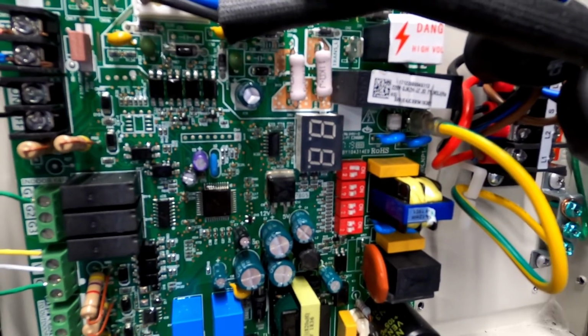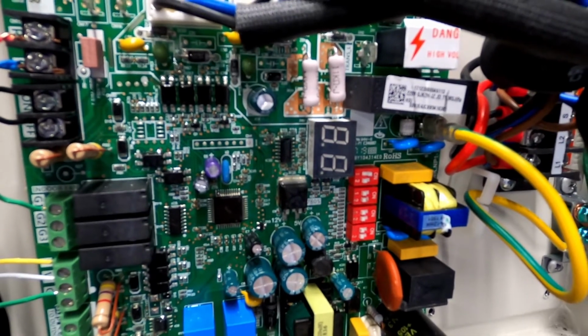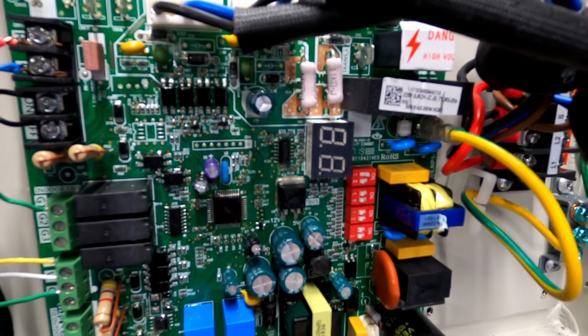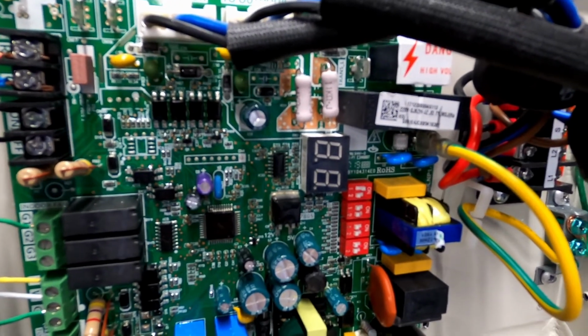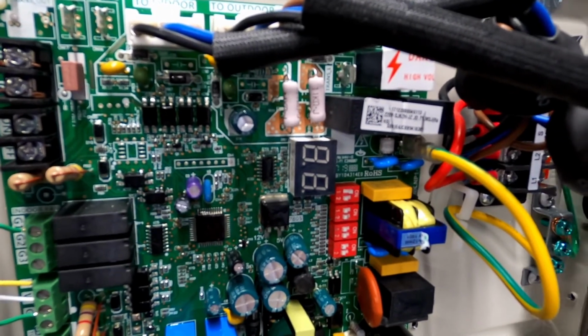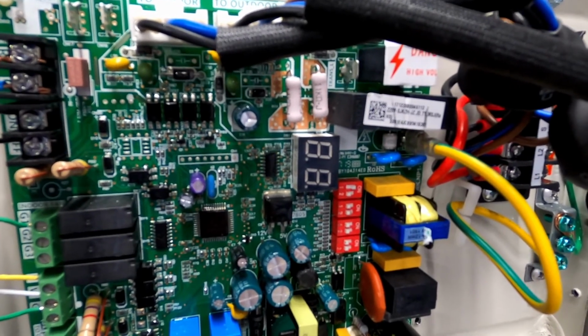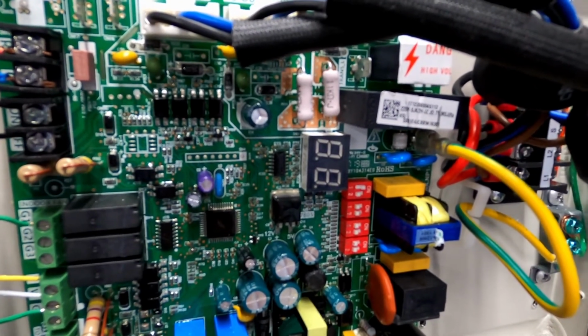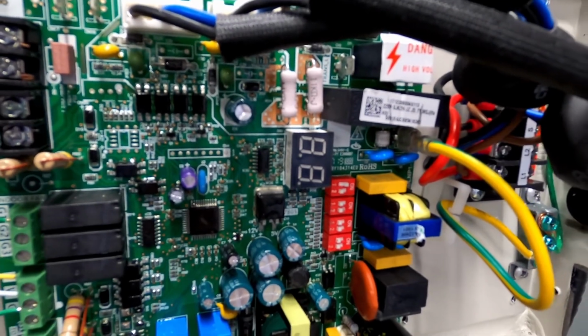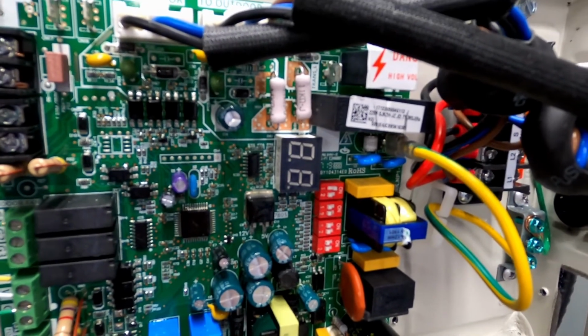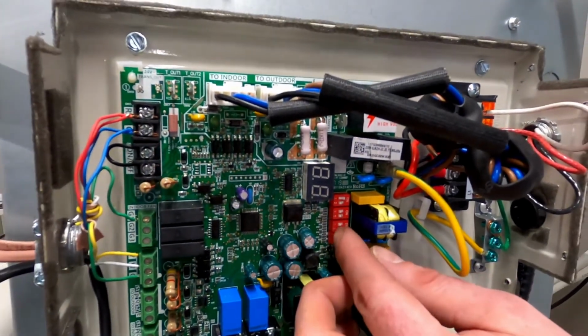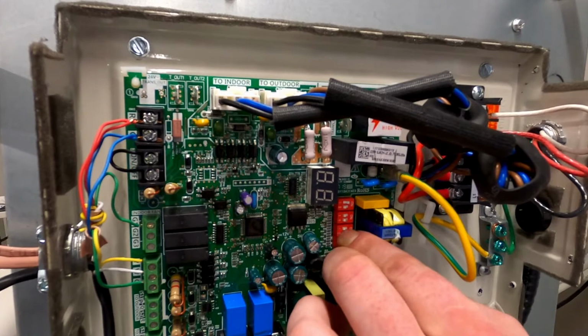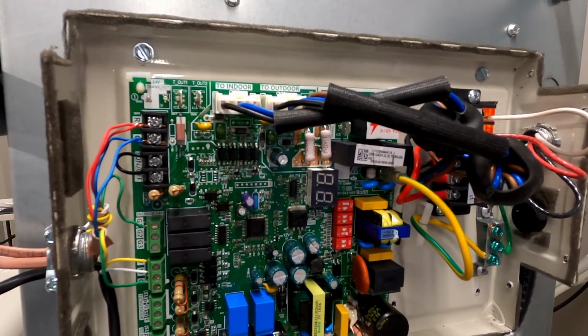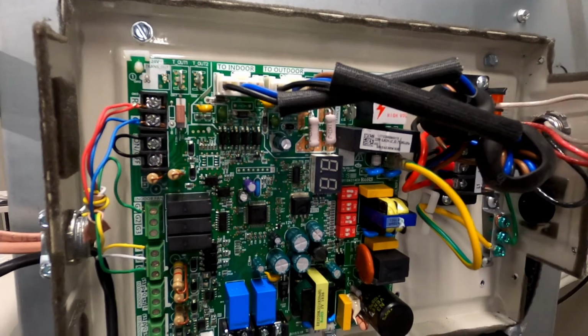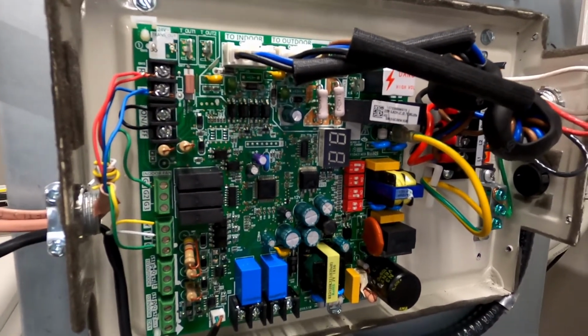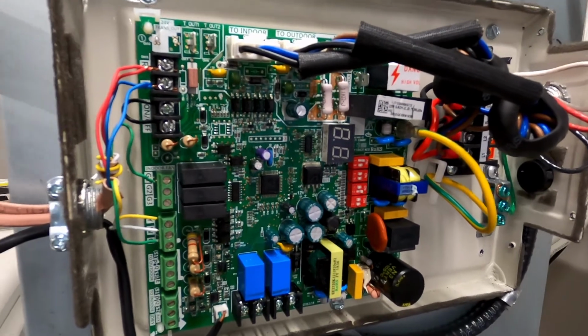3-1 should be off. That's not used. It's used for future applications. Now SW3-2 is the time, either 1 hour or 3 hours, at what point the unit will speed up to quickly meet the demand if it hasn't met it yet. I recommend turning that one to on to set it for 1 hour in case it's running for a long period and not meeting the demand. Then SW4-1 and 4-2 will also remain off as they're going to be used in future applications.